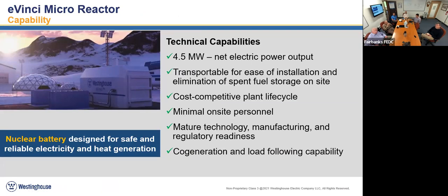I put 4.5 megawatt electric, but it's really anywhere from 4 to maybe 5.3 or 5.4 megawatt electric. It's somewhat dependent on ambient temperature. Colder is better, so in some areas of Alaska and northern Canada we can probably push that 5.3 or 5.4 megawatts electric. Most power conversion systems perform better with that big delta T for ambient temperature, but ours is fairly sensitive to it since we're using an open air Brayton type power conversion process.